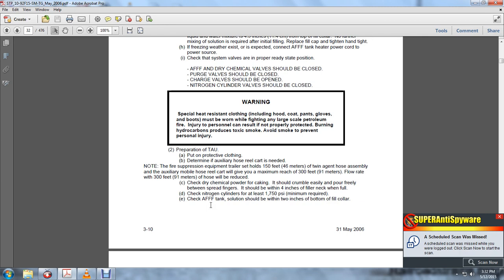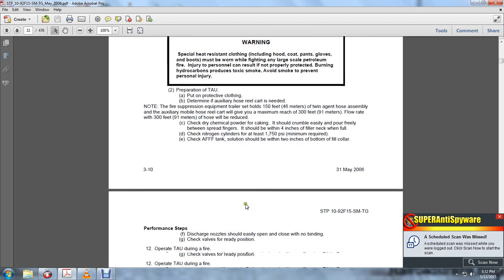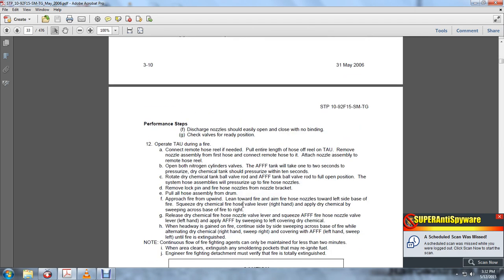Check the dry chemical powder for caking. It should pour freely or spread between the fingers, and should be within 4 inches of the filler neck when full. Check the nitrogen cylinders; at least 1,750 psi is minimum required. Check that the AFFF tank solution is within 2 inches of the bottom of the fill collar. Discharge the nozzle. It should easily open and close without binding. Check the valves for ready position.